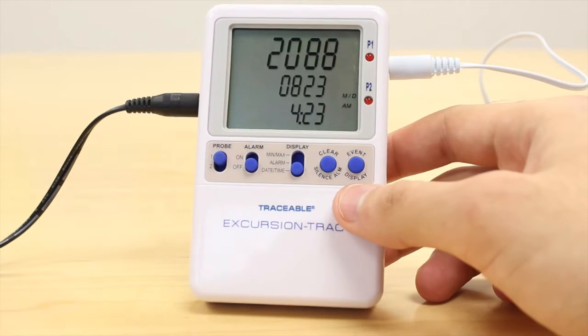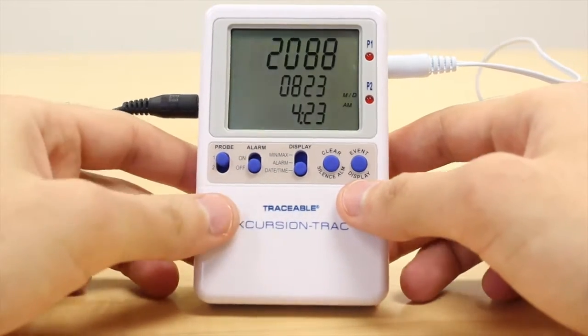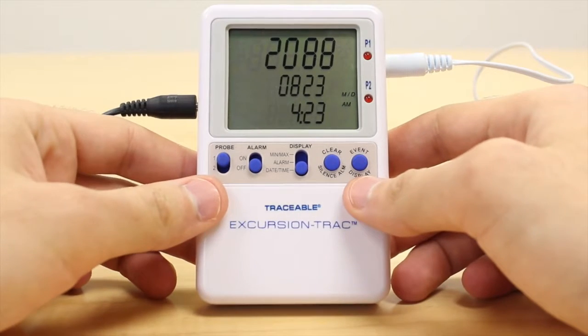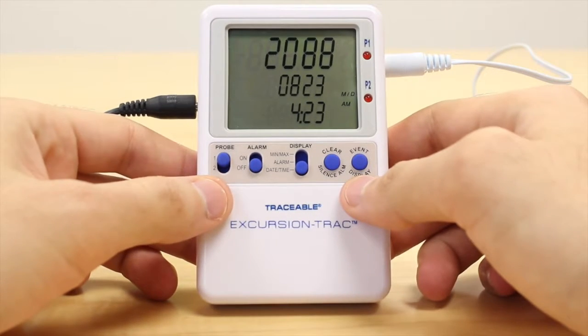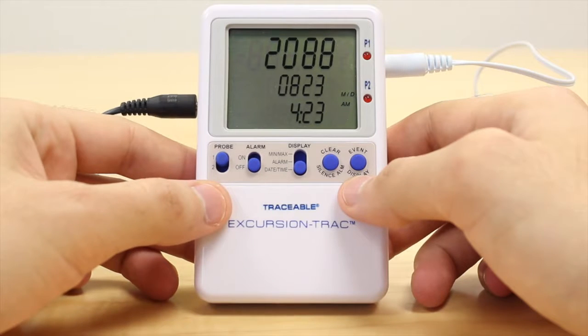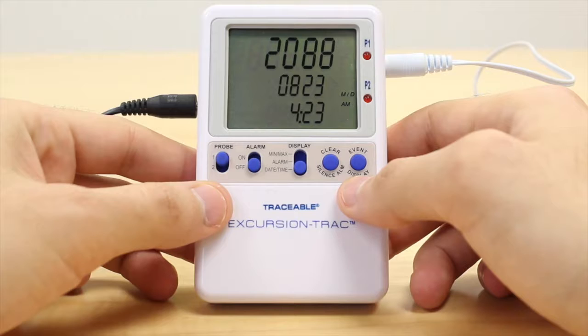Alarms are incredibly useful in alerting you when the environment you're measuring leaves your desired temperature range. Your Excursion-Trac thermometer is capable of having a settable high and low alarm for each individual probe connected, and it will alarm you visually with a flash and audibly with a loud alarm.